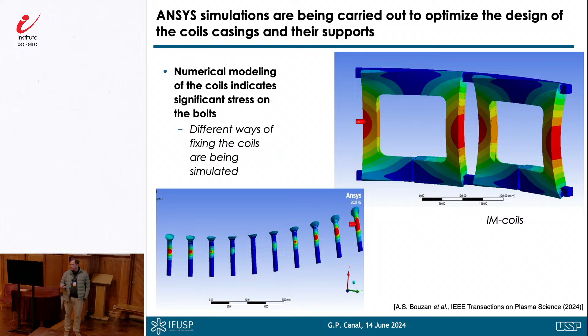We also tested how the temperature of the coils will rise over a day of operation. The red curve, for example, is the temperature of the wire in the very center of the coil. Around the wires we have the coil casing, a metal casing that houses the conductors, and then we have the bolts. The bolts don't heat up much over a day of operation, but the wires can heat up, and the wires have an insulator that can support only up to 250 degrees.